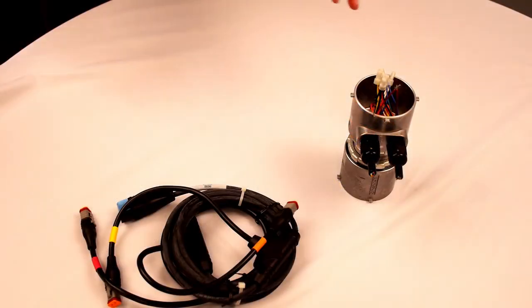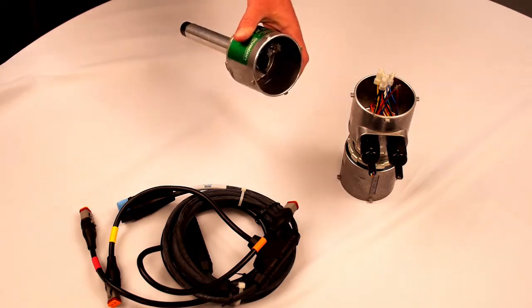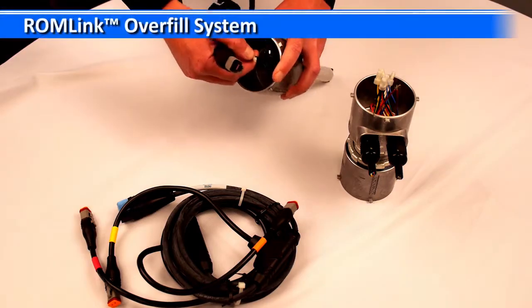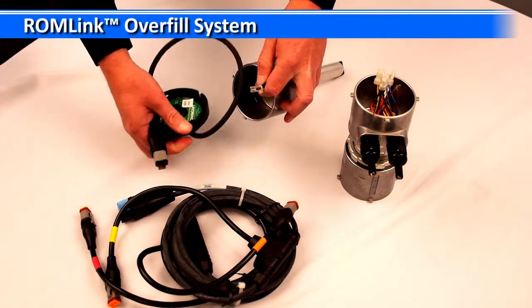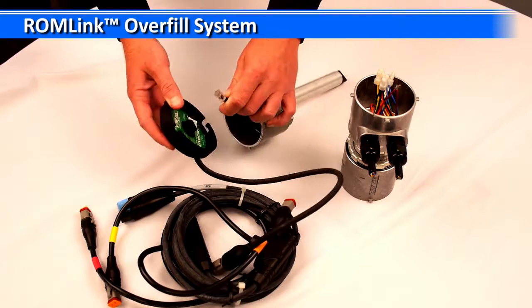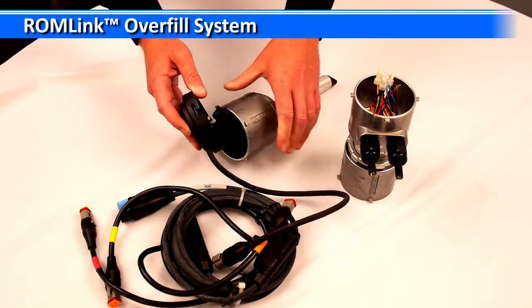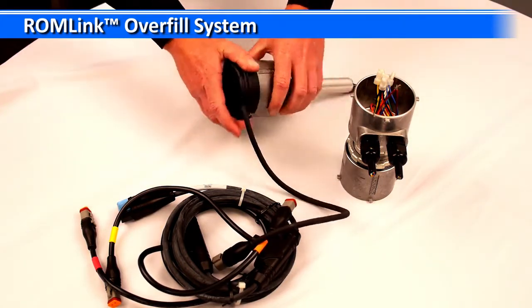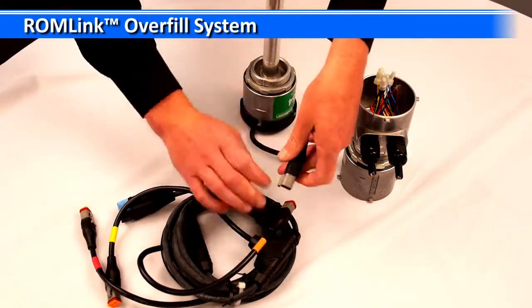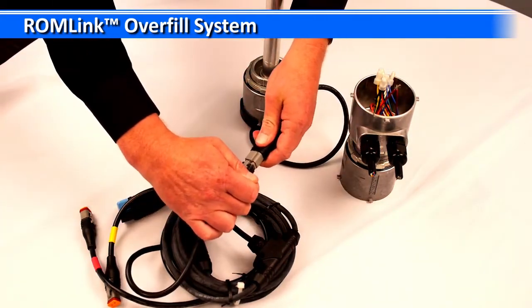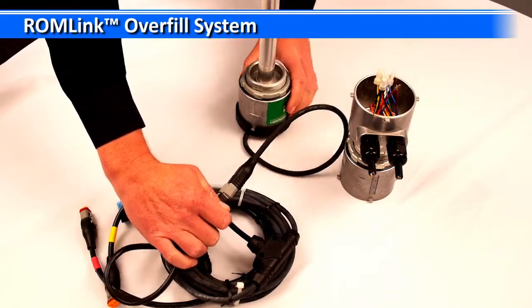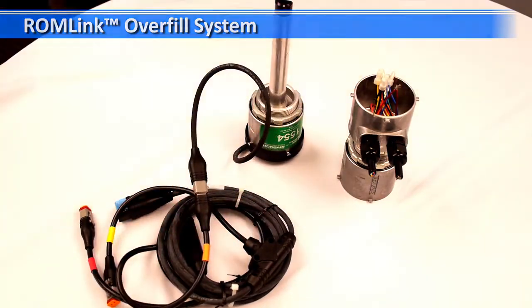Here we have the example of the 2-wire hardwire overfill system. I just wanted to show a quick comparison on some of the newer plug-in load style overfill systems. Here's the same probe, just with a plug-in connection. If you were to wire this probe up, you would simply take the cap, plug in this connection here, put your lid on, plug in to the main wiring loom. So right there, essentially, we have the same connections made.